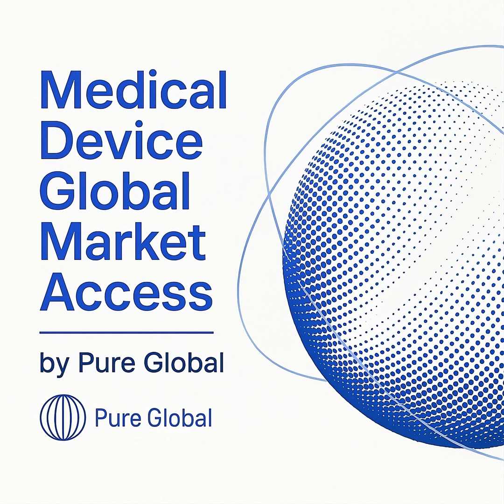Class 2A represents low to medium risk, like hearing aids. Class 2B is for medium to high-risk devices, such as ventilators and infusion pumps. Class 3, as in the US, is for the highest risk devices, like breast implants and deep brain stimulators.